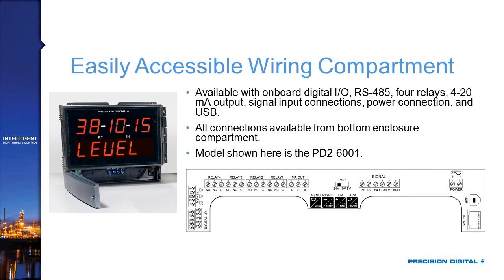The picture on the lower right shows you can get this with onboard digital inputs and outputs — the digital outputs can go to a PLC for alarming, or I can use the digital inputs for an external control station with remote buttons for control or programming. I can have RS-485 for Modbus communication, four relays for control and alarming, a 4 to 20 milliamp output to send back to the control room, and signal input connections including P-plus, P-minus power supply to run my transmitter or 4 to 20 input loop.